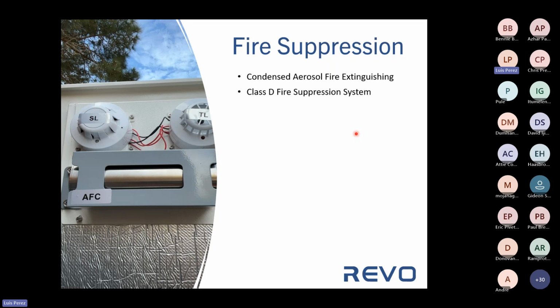This type of fire is actually called Class D. The type of system we utilize is a flooding type, even though it uses particles. It uses ultrafine potassium salt particles, which are atomized by this cartridge mounted on the door. Of course, it doesn't have the drawbacks of using a gas type of system, especially because some of the gases are not friendly to the ozone layer - they're greenhouse gases.